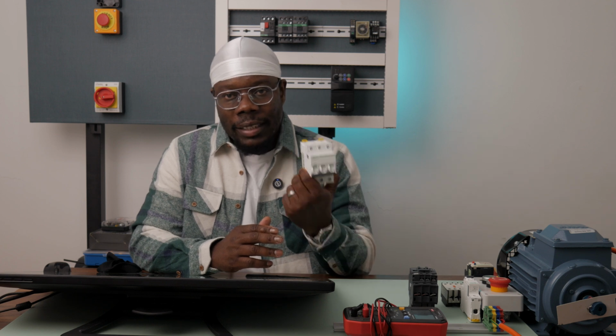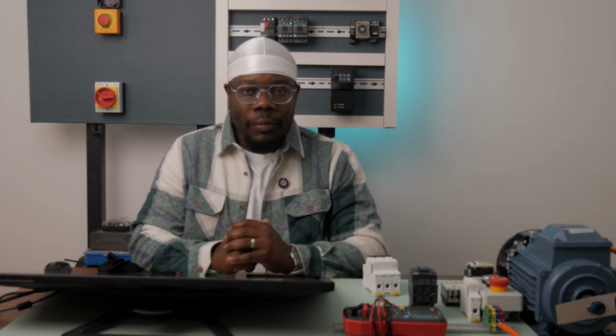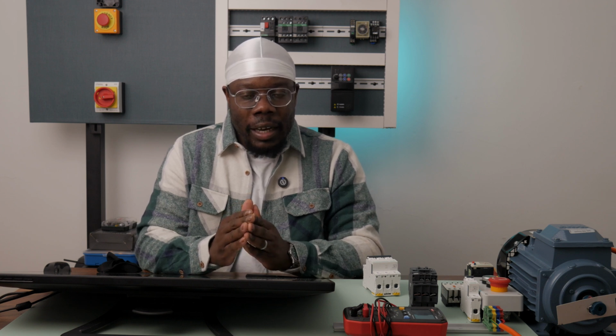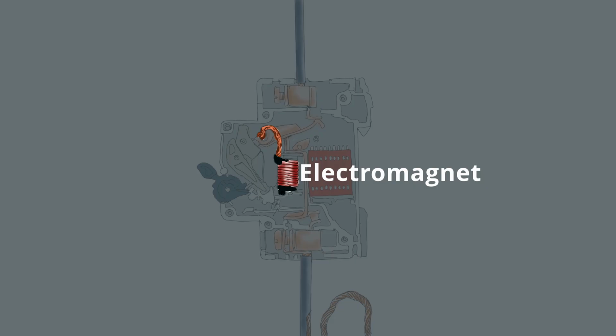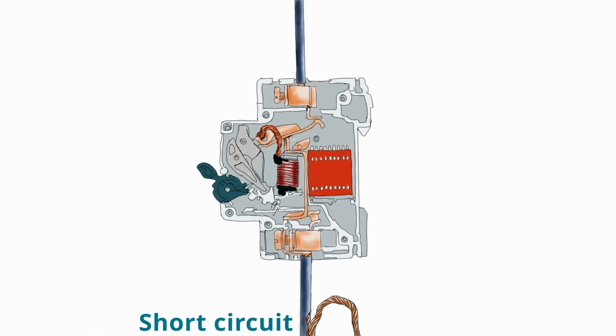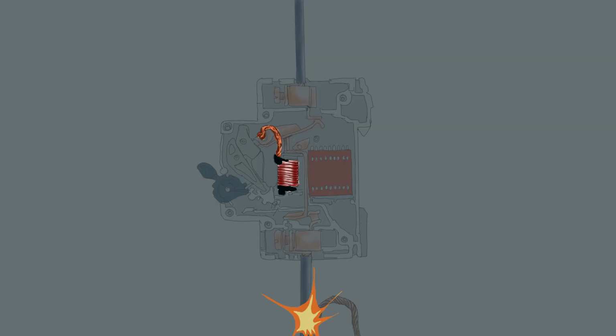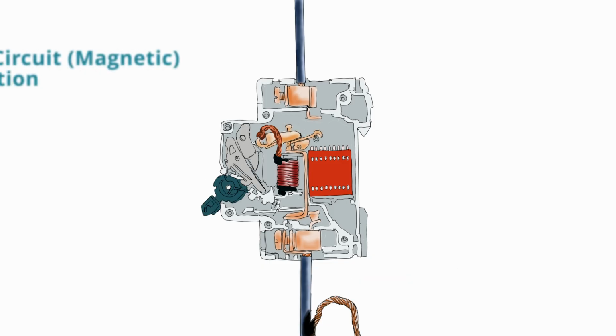So due to the magnitude of short circuit currents, we want these fault currents to be extinguished immediately. So we rely on the circuit breaker to do just that. The type of protection that we get from a circuit breaker is called magnetic protection, because those large fault currents activate the magnetic component of the circuit breaker, which ultimately extinguishes our short circuit current. Now let's discuss how a circuit breaker stops short circuit currents. Inside a circuit breaker is an electromagnet that activates when there is a sudden surge of current. The strong magnetic force pulls open the switch, stopping the flow of current and avoiding damage to cables and electrical equipment.